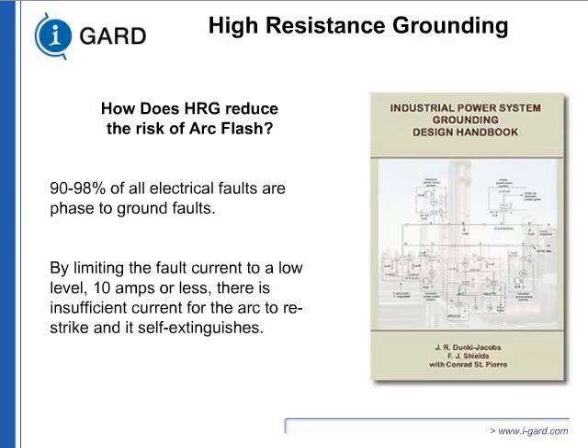It doesn't reduce it if a three-phase bolted fault happens, but three-phase bolted faults are very rare, mostly happening because of human error or something like that. In my 40 plus years of experience, I've only found 4 cases of bolted fault. And unfortunately, in all of those places we had left the jumpers on after the testing. We didn't remove the grounding jumpers. So that's why Dunki-Jacobs' book says, and 70E also will tell you, that it will mitigate the risk. Right?